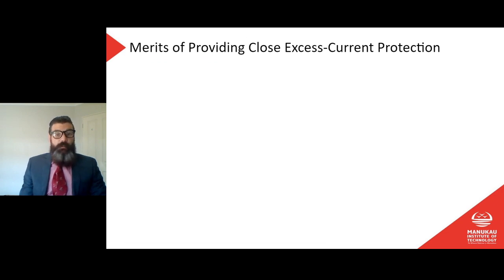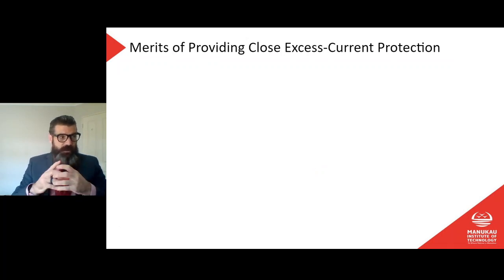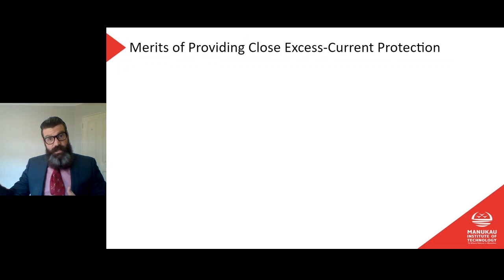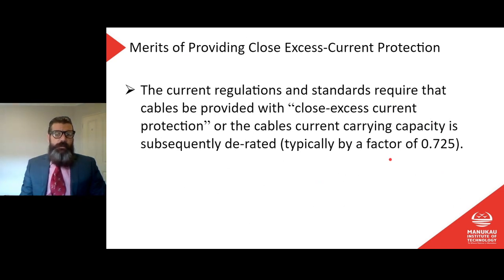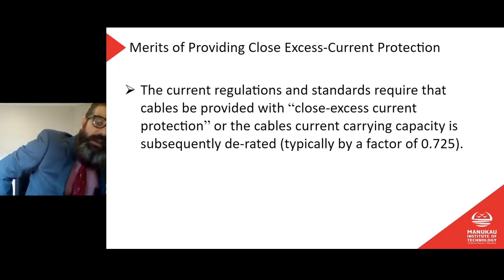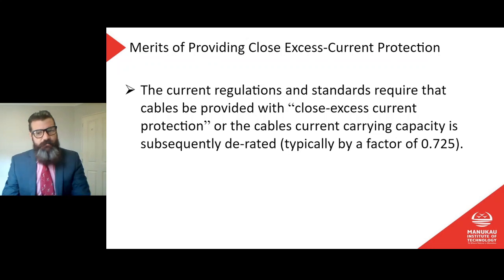Right, merits of providing close excess current protection. So why would we provide close excess current protection instead of coarse excess current protection? Remembering, of course, that close means it will trip in 4 hours or less at 1.5 times the rated current, coarse protection being more than 4 hours at 1.5 times the rated current. So the current regulations and standards require that cables be provided with close excess current protection, or the cable's current carrying capacity is subsequently derated, typically by a factor of 0.725.